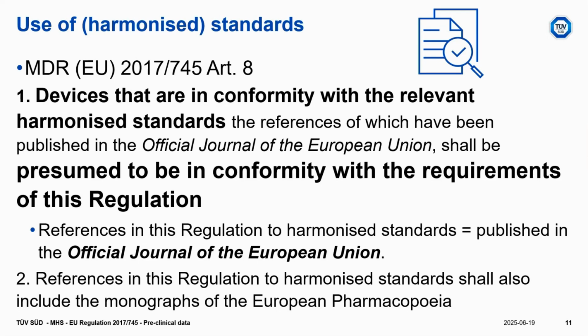So just consider that, for example, if you mention a certain standard on the labeling, on the instructions for use, or in the technical specification of your device, in that case the standard becomes the performance claim or a safety claim, and automatically the notified body will go very deep in the assessment of your application. Or if you claim a certain standard in your GSPR and you say that you apply it, and there is any incomplete application or not full conformity of the device, for us, if you show that you apply the standard in the GSPR, then the standard becomes mandatory.